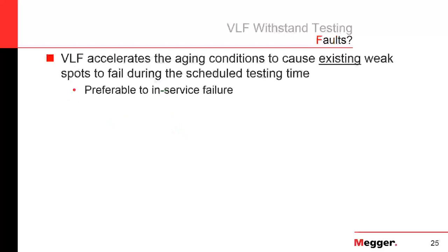So I've been talking about faults a bit here, and that might be a little off-putting to some people. You're saying, I'm going to put faults into your cable. Well, that's not the case. VLF only accelerates the aging conditions that already exist in the cable. It causes them to fail during our scheduled testing time, and that's preferable to having that fail unexpectedly in service.